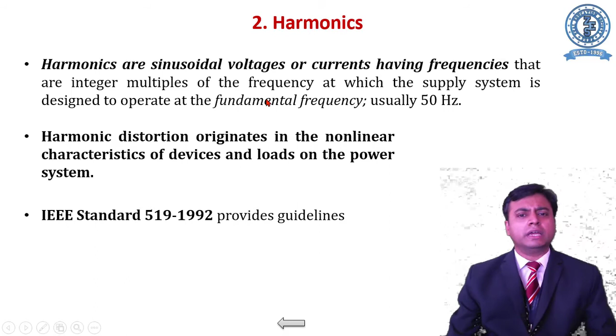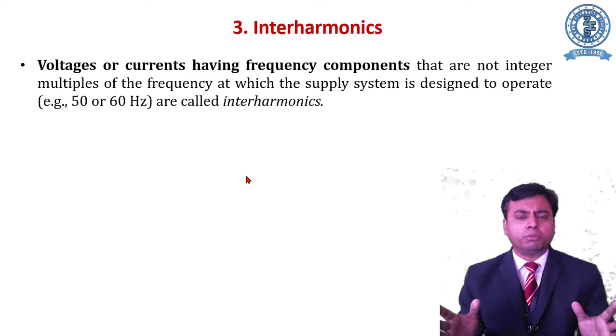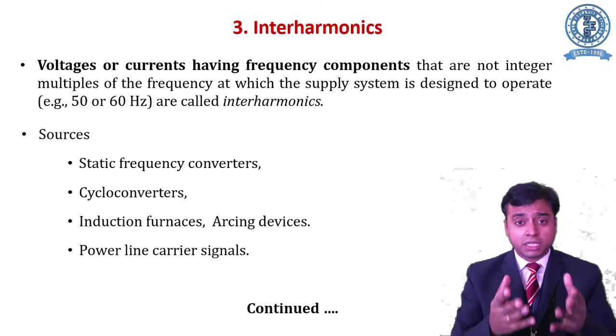Next we will move on to interharmonics. What is interharmonics? It's very simple to understand. These are voltages or currents which have a frequency that is not an integer multiple. Previously you had integer multiples: 3 times, 5 times, 7 times. Any other component which is not an integer multiple will be treated as interharmonics. What are the possible sources? Static frequency converters, cycloconverters, induction furnaces, arcing devices, power line carrier signals. These are some of the sources which will give you interharmonics in the system.